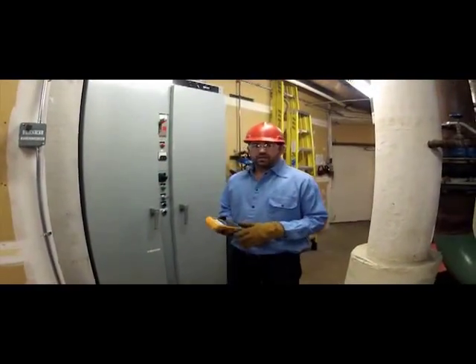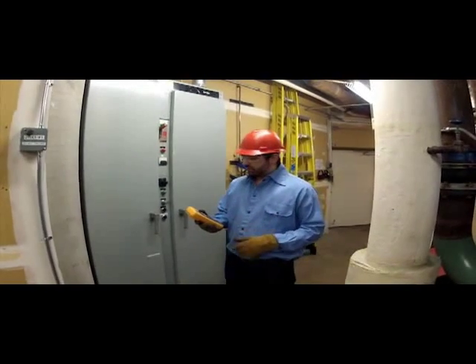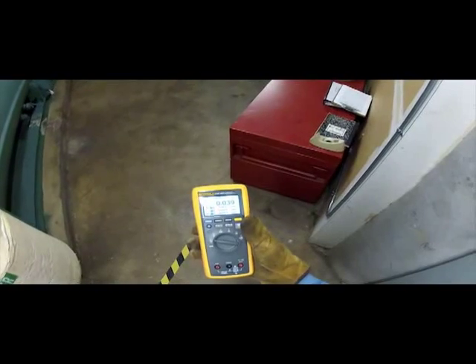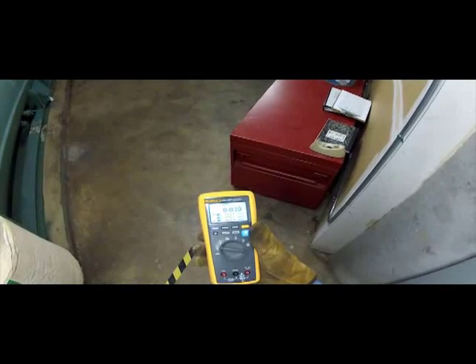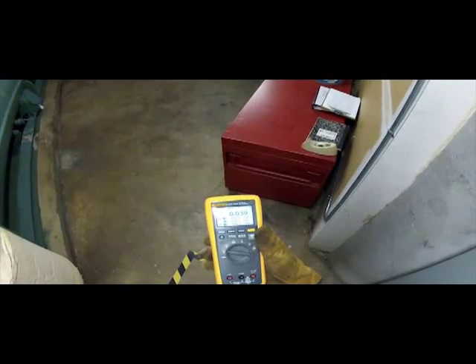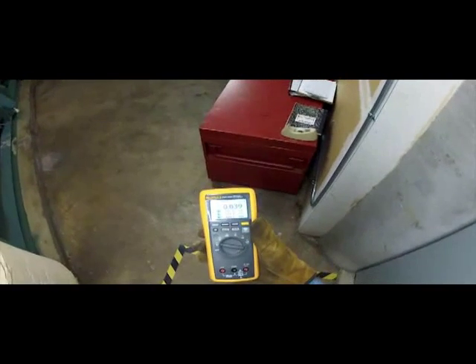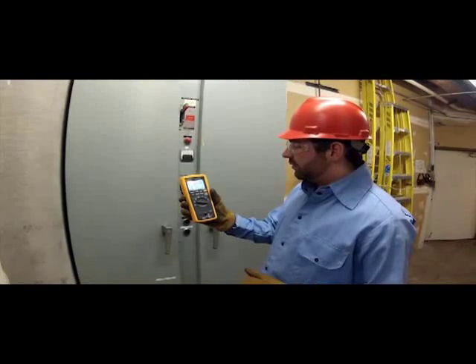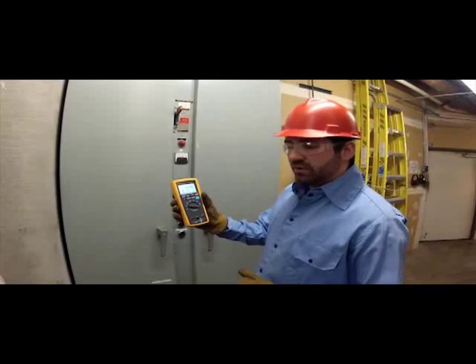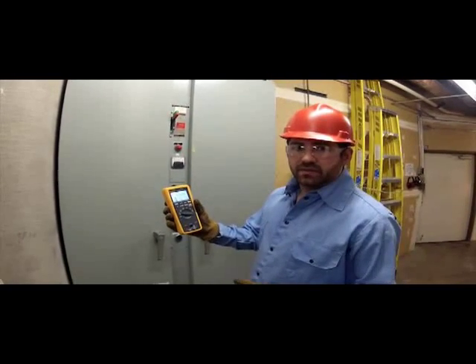So now that I've re-energized the piece of equipment and we're running, I've connected to my three wireless modules inside the cabinet, and as you can see, we are monitoring each phase running through and to our machine currently. We're going to leave this here and let it log throughout the day so that we can trend and build a baseline for this piece of machinery.